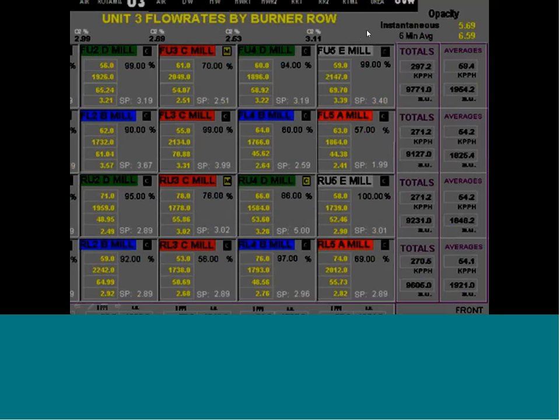If you're measuring CO, you're going to see much less CO because you have good combustion at each and every one of these burners. So even if using coal valves, we couldn't balance this, say the FL4 and the FL5 burners. They're not perfectly balanced in terms of mass of coal. We use those air registers to very easily adjust them to bring the right air-to-fuel ratio to each burner.